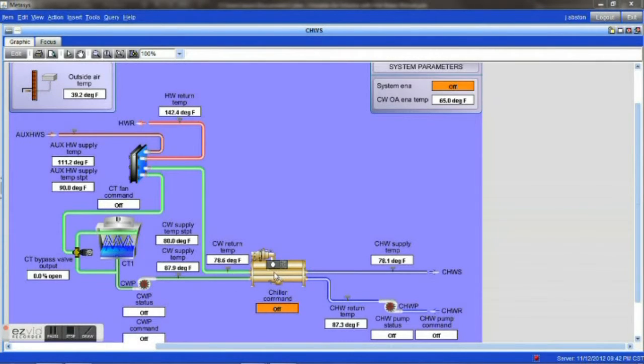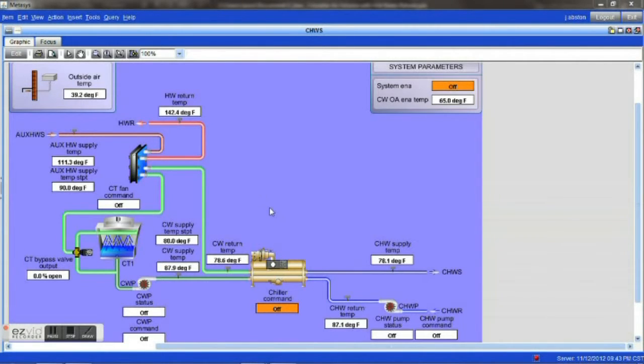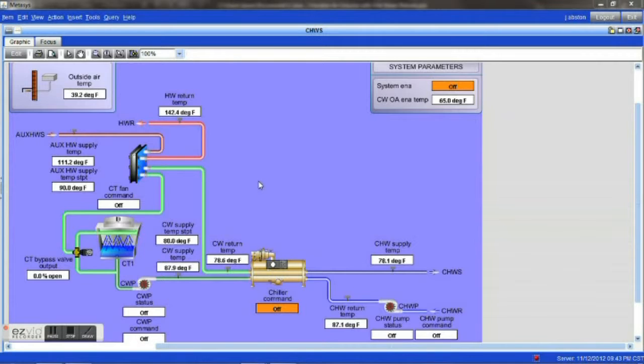We want to make sure that we keep the chiller supplied with adequate temperature on our condenser loop. If we do not move the heat off of that machine, you can damage your machine. It's very inefficient. If you get it hot enough, you can actually vent some of your coolant from the system.